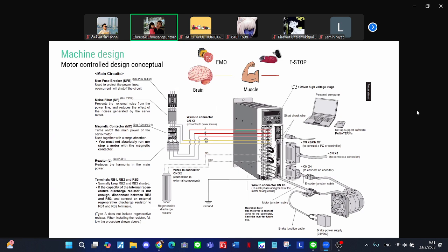but if we use separate power between the controller and drive, we can do quick recoveries. It may be down to 3 minutes to recover, because we cut only some part when we open the door, just only the drive one. It means the muscle is stopped, but the brain still remembers. So any questions so far?